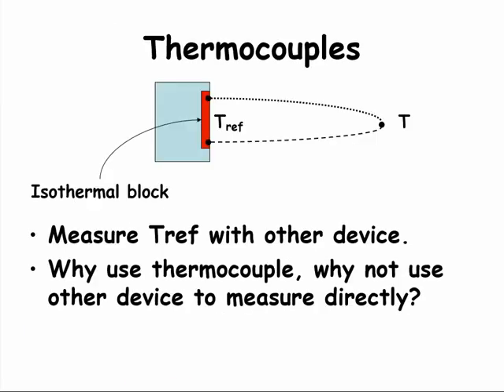This slide illustrates how we connect thermocouples to our meter. We have an isothermal block which serves as a reference temperature, which we need to measure with another device. So if we need another temperature sensor in the meter, why use a thermocouple? Why not use the other temperature sensor? Well, the answer lies among the advantages of thermocouples seen at the beginning of this video. Thermocouples are rugged, inexpensive, work over wide temperature ranges, and provide adequate precision. The other sensors — RTDs, thermistors, and integrated circuits — have disadvantages that make thermocouples a popular choice.